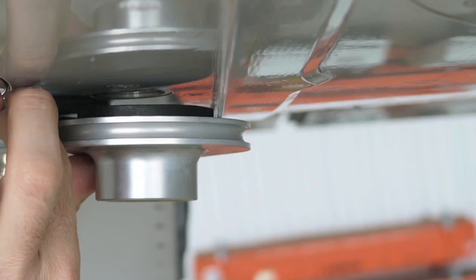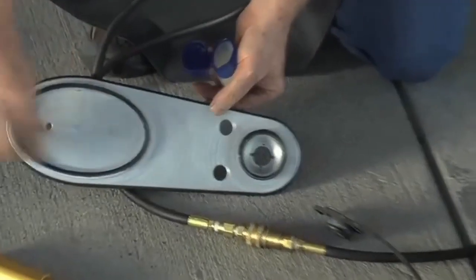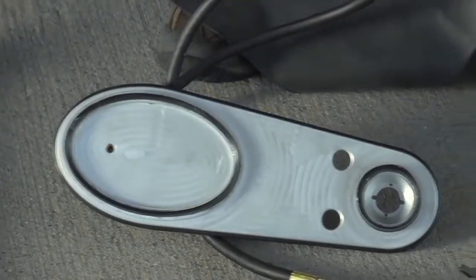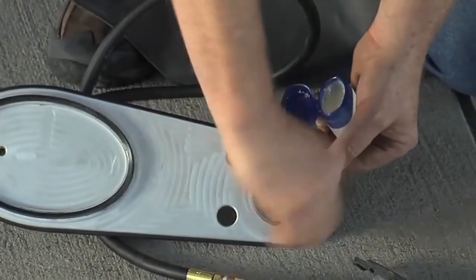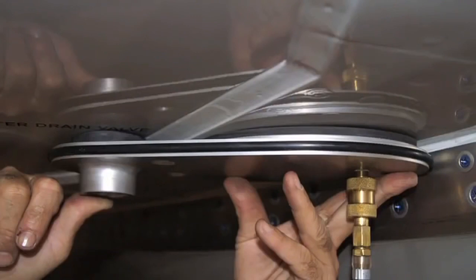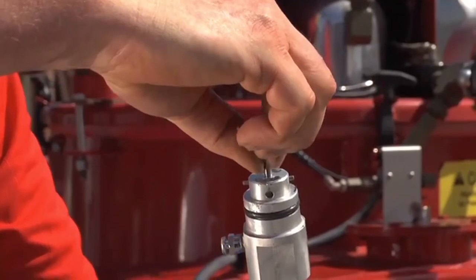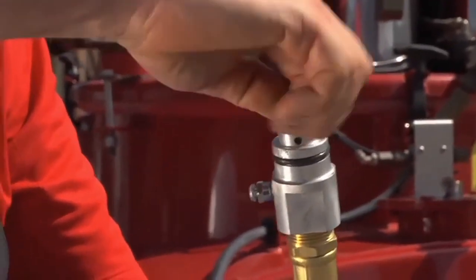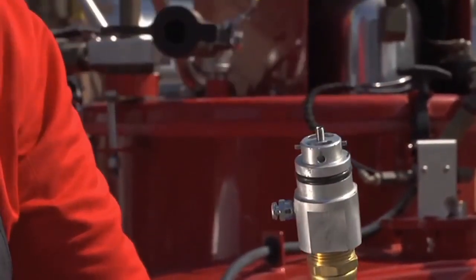If not possible, liberal application of the supplied petroleum jelly to the seal will help the drain tool seal adapt to uneven surfaces. This grease will also help the seal splay out against the skin to further improve the tool's adherence. When one has a drain tool selected, we need to install a probe pin into the fuel probe pigtail assembly. The supplied pin kit contains a selection of pins in varied lengths.